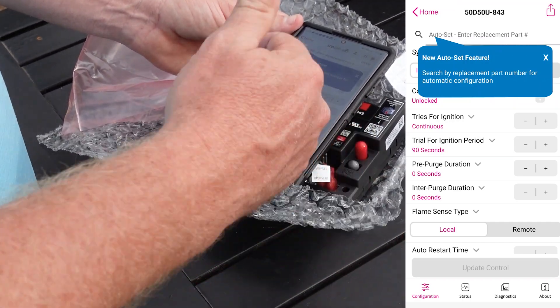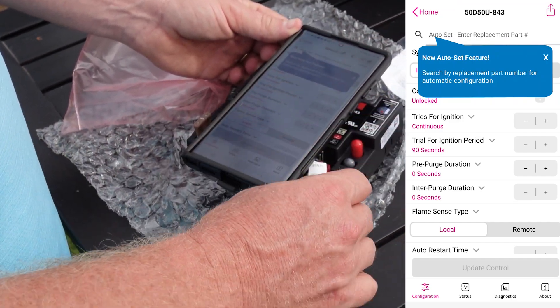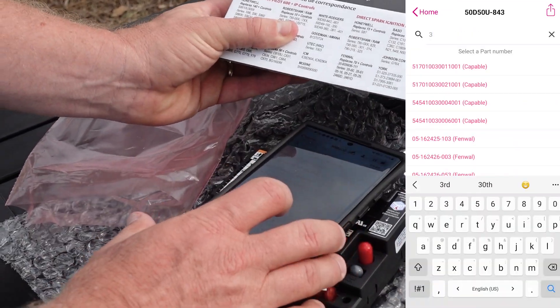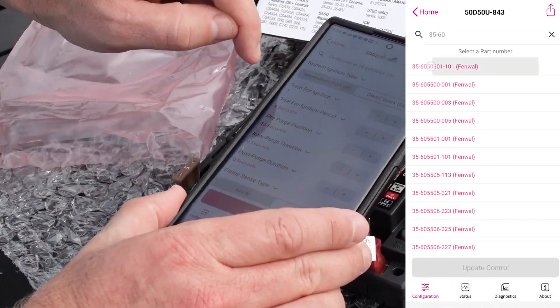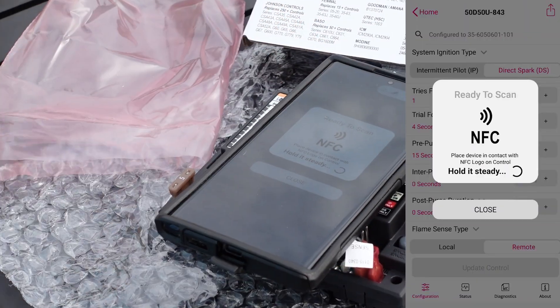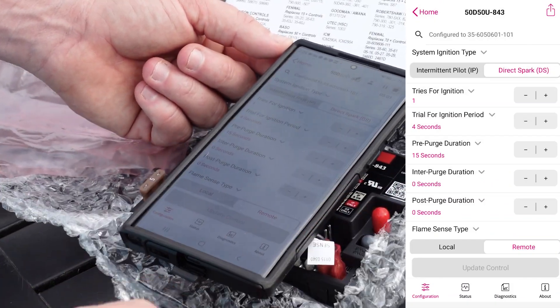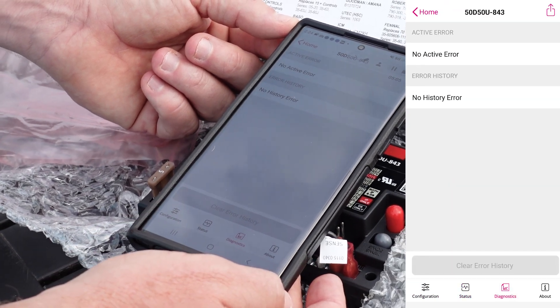The AllSpark can replace over 1,000 OEM parts, so the automatic configuration of the White-Rodgers Connect app saves a lot of time. For example, when replacing a Fenwal control, it automatically sets up all the parameters needed to match the control we're replacing. We just have to hit Update Control and keep the mobile device near the AllSpark, and the control is updated with all those new configurations. While it's operating, we can look at system status and diagnostics, making it more capable than the modules that were in place before.